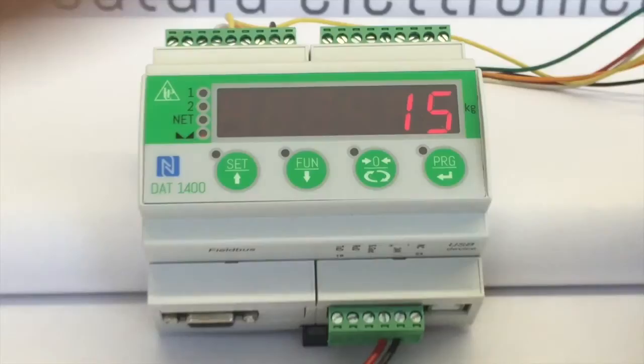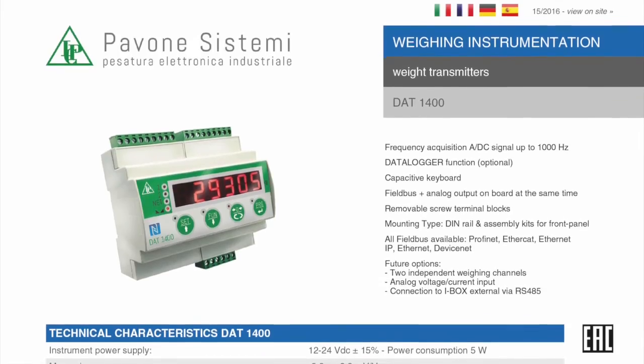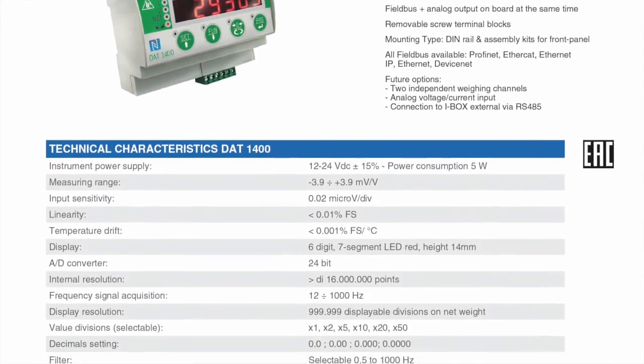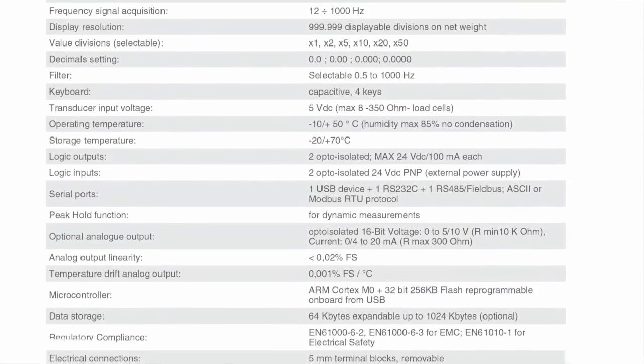The value visualized on the display is now the weight of the system itself. Enter this value in the DEADL parameter by following the previous steps. Now you have configured the instrument.